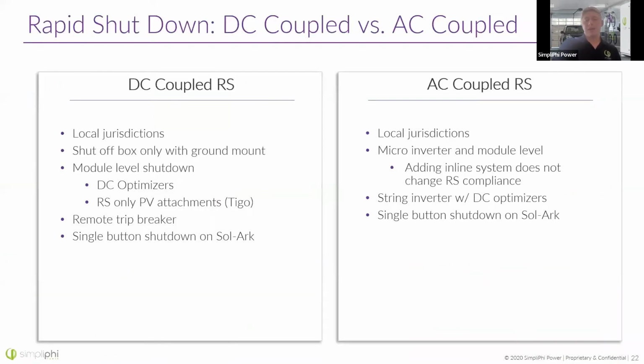So rapid shutdown is a highly debated topic amongst DC versus AC coupled systems, and really it's not that different. I think what's causing it to differ more is where you live and your jurisdiction's requirements. So always, first off, as a disclaimer, always check with your local jurisdiction and make sure you understand what your inspector wants to see on your rapid shutdown. Some of them, if you've got a ground mount system, you can often get away with just a shutoff box for that ground mount array. But if you've got panels on your roof, many times you're required to have module level shutdown, which is either a DC optimizer for your DC coupled array or rapid shutdown only attachments. Tigo makes both of these as an example.